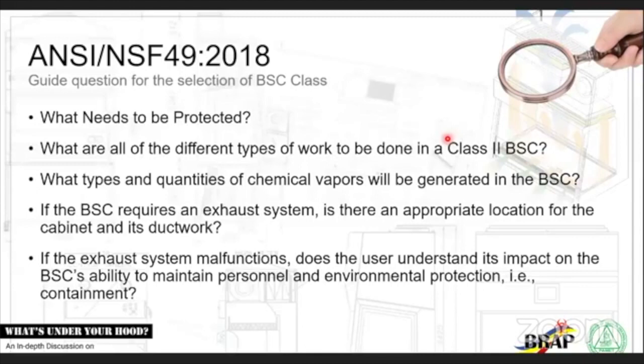Now the fourth question: if the biosafety cabinet requires an exhaust system, is there an appropriate location for the cabinet and its ductwork? Again, in the Philippines, the building always comes first before the planning, and that's one of our gaps in the laboratory. We want to put up the laboratory as fast as we can. However, we forget to look into the finer details, and this is one of the most overlooked parts. If you plan to place your exhaust, make sure to place your laboratory at the far end of the building, away from adjacent buildings and away from residences.